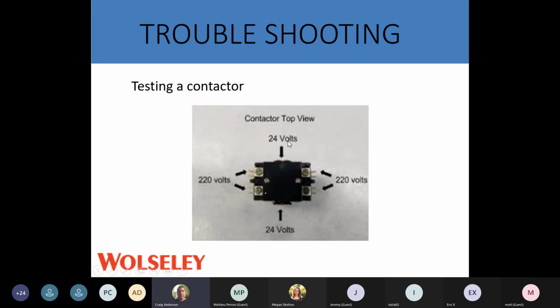So you want 24 volts on each side of the contactor when we're testing it, and 220 volts from L1 to L2. When we're testing L1 to L2, we're putting our multimeter on L1 and L2 to get our 220 volts. Some panels will allow you to put a breaker in, and it'll only take it off one leg of the panel. So always check between L1 and L2. If you're checking your voltage outside and you go ground to L1 and ground to L2, you'll get 110 volts on each side. But when you go across your L1 and L2, you'll get 0 volts.